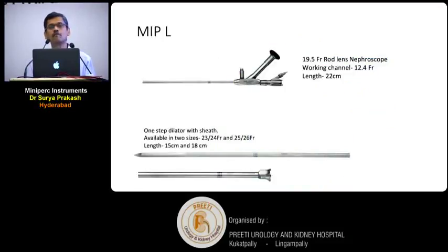This is a nephroscope from Storz called the MIP Large nephroscope. It is a 19.5 French rod-lens nephroscope with a very good working channel of 12.4 French. The length of the scope is 22 centimeters. The dilatation is by single-step dilatation — put a guidewire, then a 10 French fascial dilator, and directly put this one-step dilator. It comes in two sizes: 23×24 and 25×26. There is a sheath with this in two lengths: 15 cm and 18 cm. The 18 cm can be used for supine PCNL and obese patients.